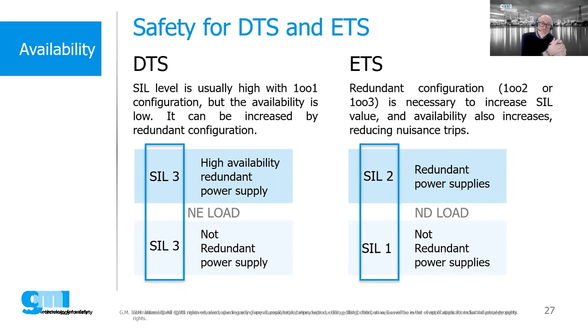As regards energized to SIF application, typically a normally de-energized load, as mentioned above, redundancy is essential to reach a SIL2 or SIL3 level. In fact, without redundancy, with a single safety power supply, only the SIL1 level can be reached, and also availability to the process is low. But by composing a configuration 1 out of 2 or 1 out of 3, it's possible to get a higher SIL level up to SIL3, and at the same time increase the availability of the process also for energized to SIF application.